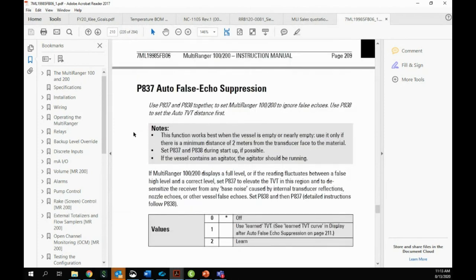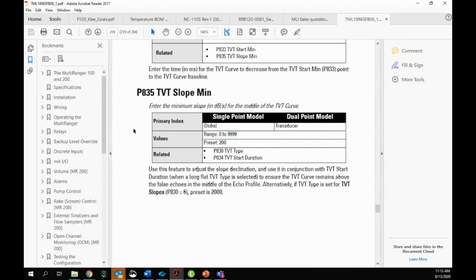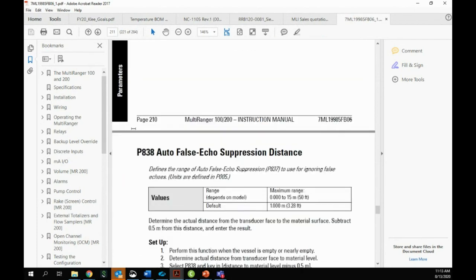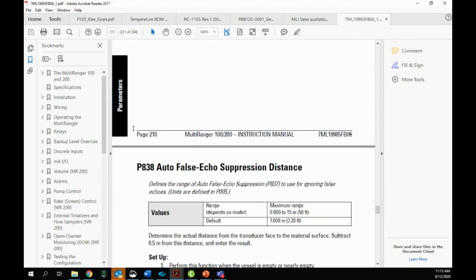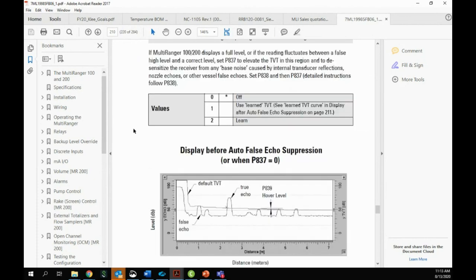P838 and 838, P837. 838, 837. Yeah, there we go. So basically, what you're going to do is enter the range in parameter number 838. You're going to say, how far do you want to learn to? Then go to parameter number 837 and perform a learn function, which on the old Hydroranger is you enter a 2. Enter the 2, wait about 3 or 4 seconds. You'll see the display screen flash a little bit. Then I'll go back and make sure that parameter number 837 is set to a 1, which is to use what you learned. So parameter number 838 and 837 are the ones that you would use for auto false echo suppression. Great question.